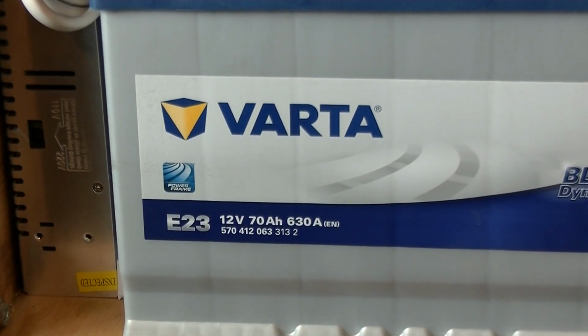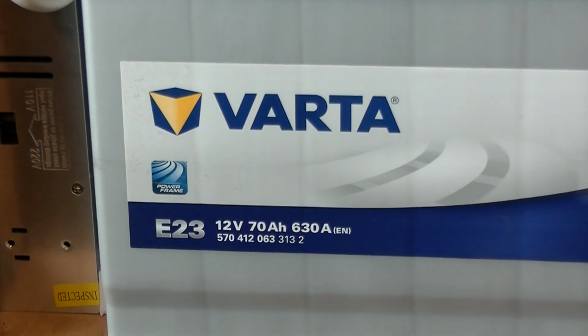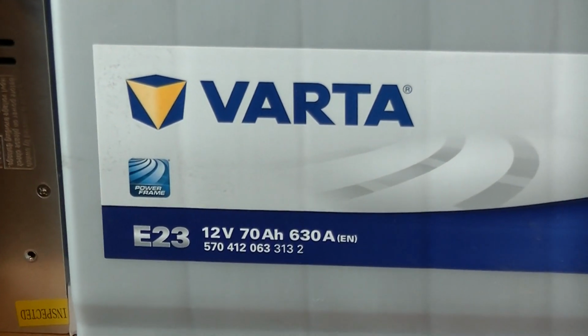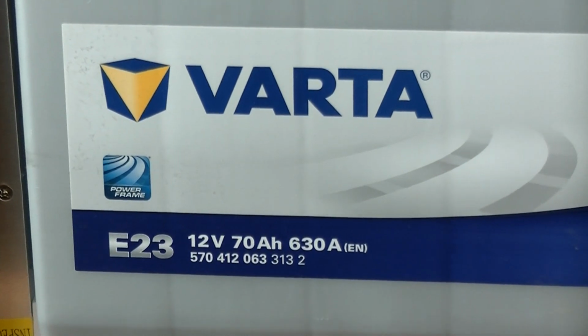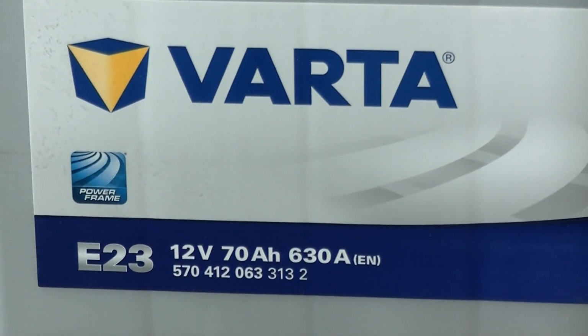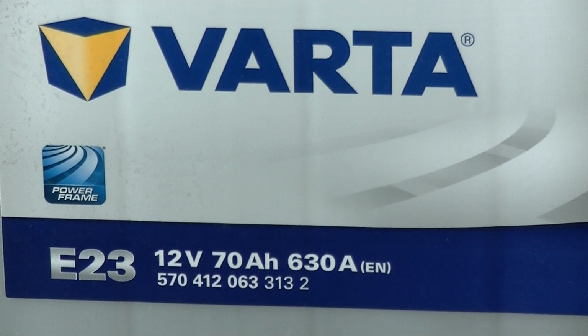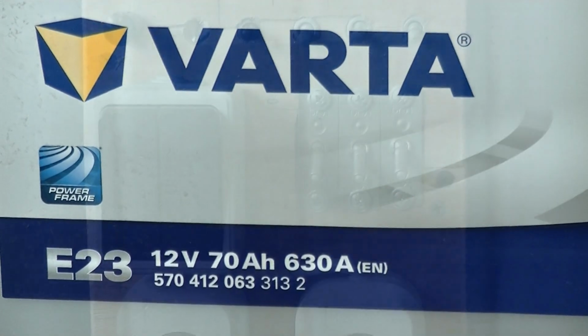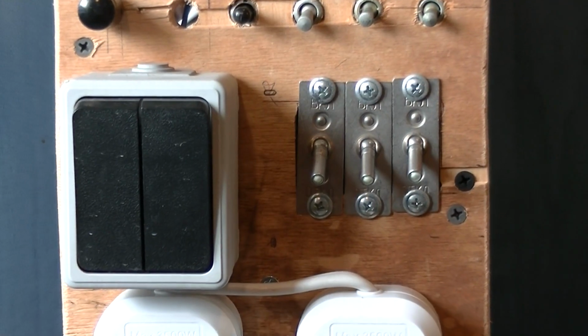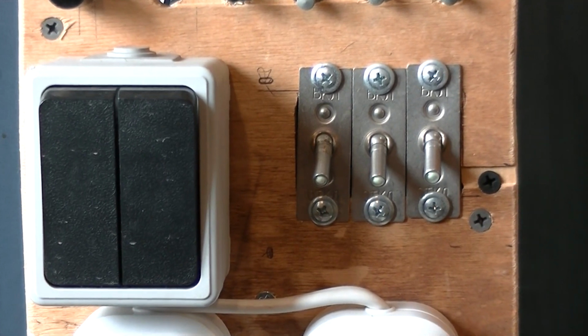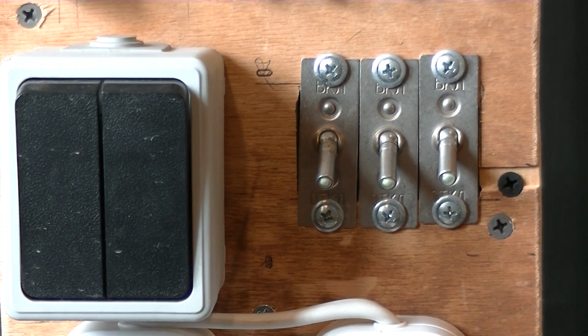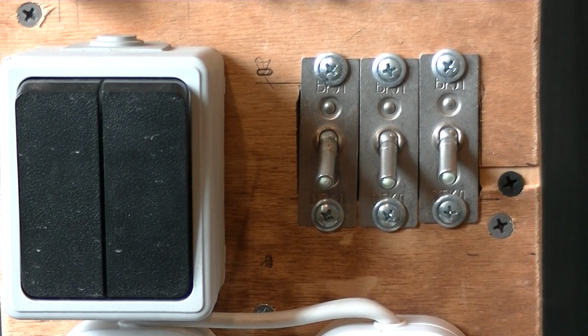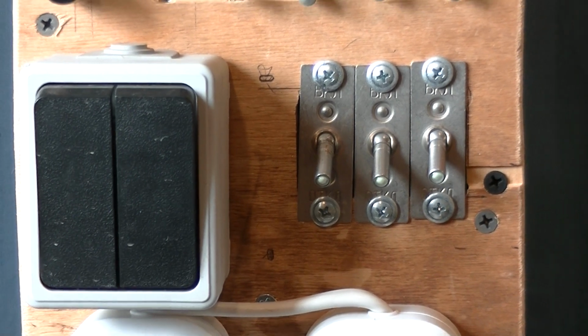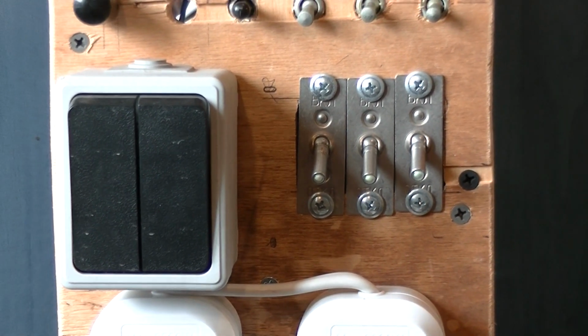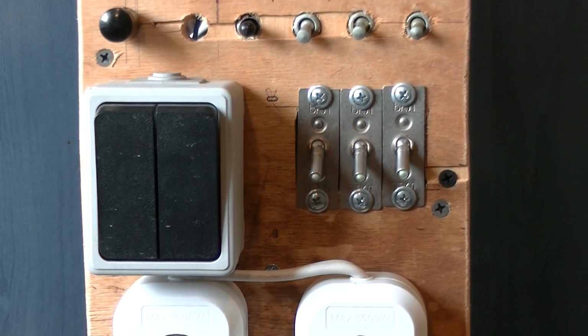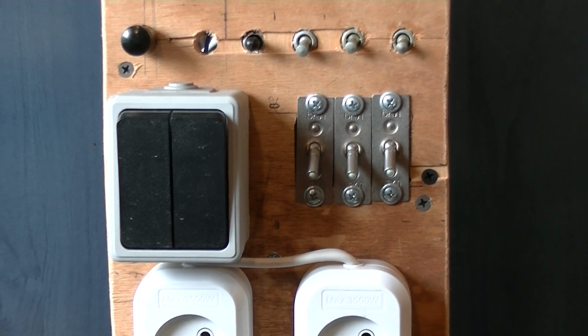To supply a rated load of 800 watts, the current of the 12 volt circuit can reach from 70 to 80 amperes. To connect the power cables from the battery to the inverter, 3 switches are used, each with a working current of 35 amps. This avoids energy loss at high currents and eliminates overheating and burning of the circuit breaker contacts.